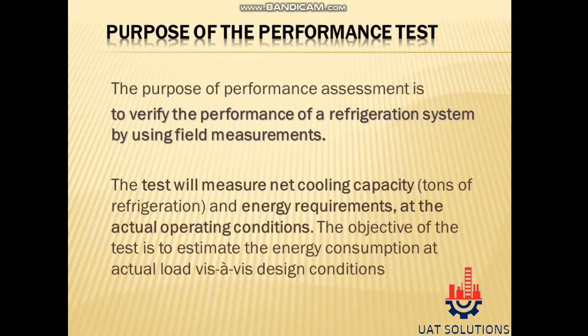Purpose of the performance test. The purpose of performance assessment is to verify the performance of a refrigeration system by using field measurements. The test will measure net cooling capacity, tons of refrigeration, and energy requirements at the actual operating conditions. The objective of the test is to estimate the energy consumption at actual load vis-a-vis design conditions.